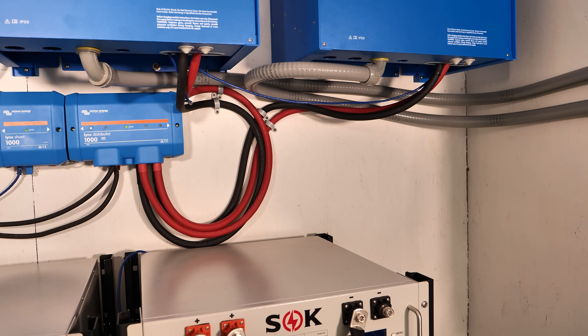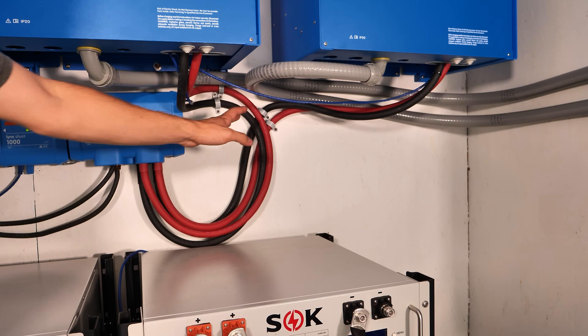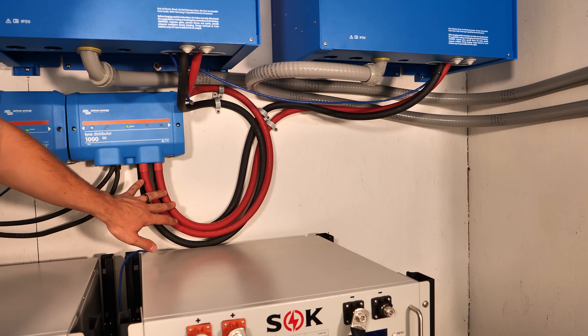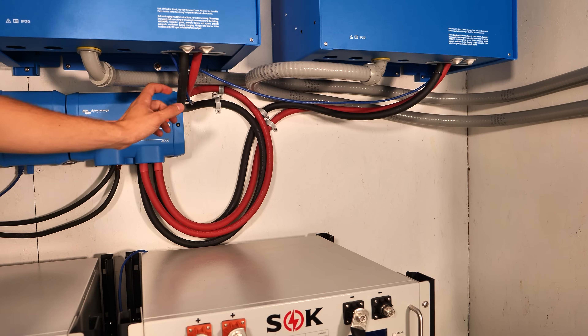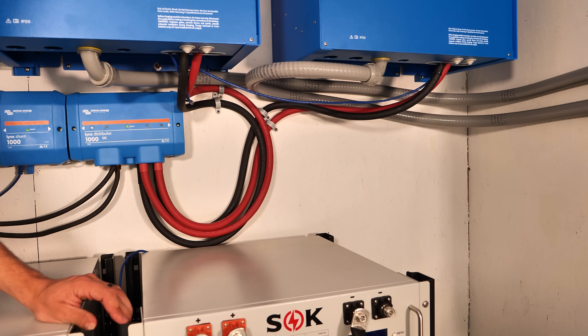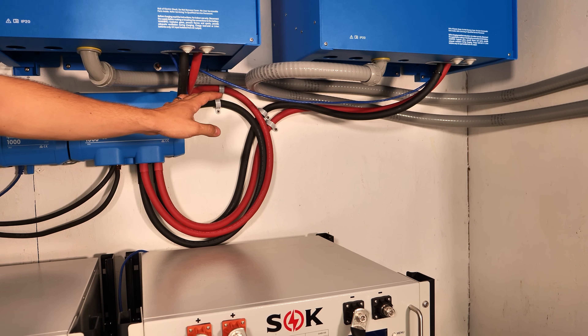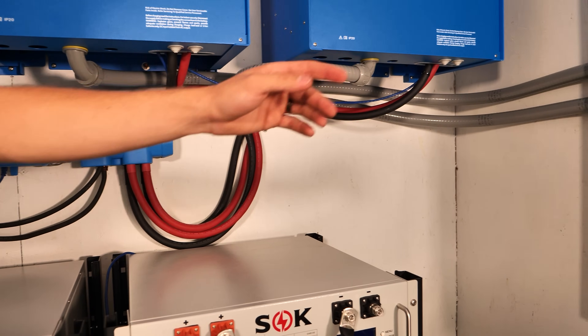When using Victron inverters in parallel, things need to be equal — so the battery cables here are equal length. These are pre-made cables from Current Connected: four-foot length, 4/0-gauge, hydraulically crimped with a 10,000 PSI hydraulic crimper. The AC output runs through one-inch seal tight with two-gauge wire over to a load center readily available from Home Depot.